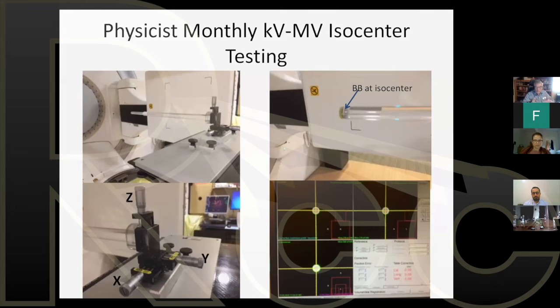Don't forget, the machine has both imaging and megavoltage, and they're 90 degrees apart. So each has its own isocenter. The two have to be perfectly aligned. If you want to target an image exactly where you're treating, you need to run this test to make sure that your image isocenter precisely coincides with your MV isocenter. This is called a Winston-Lutz test, or Elekta calls it a flex map test.